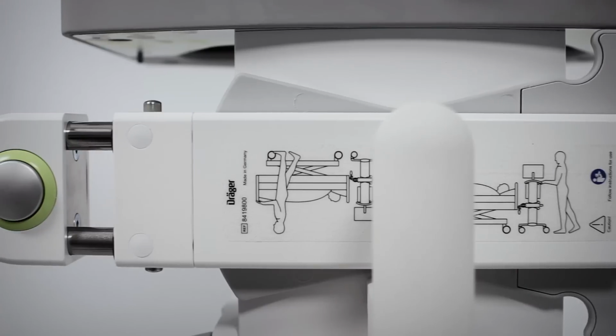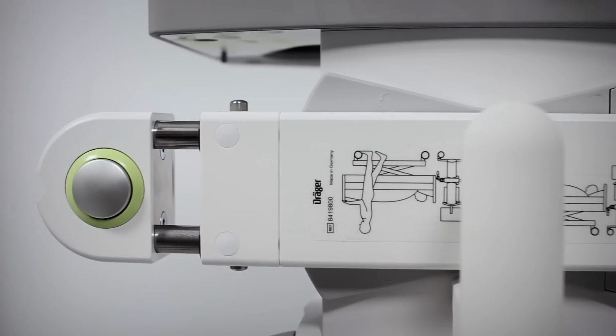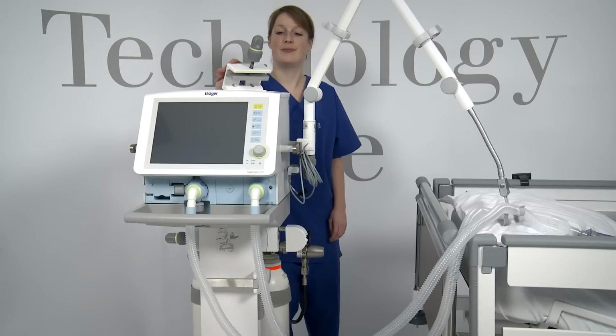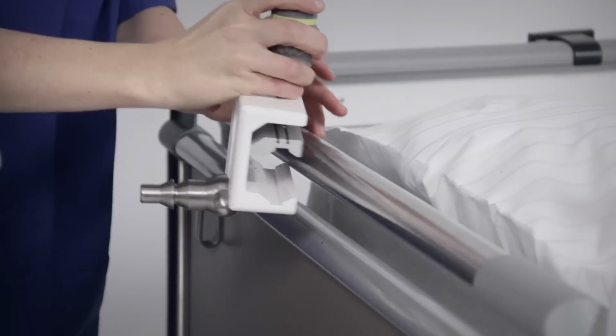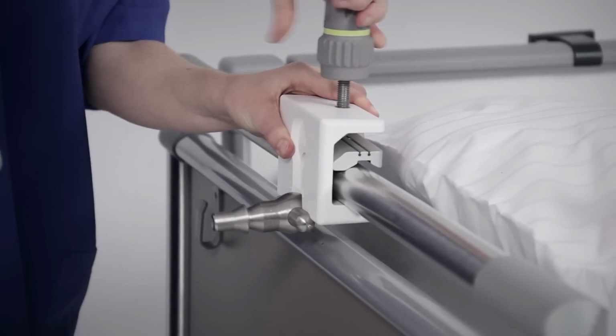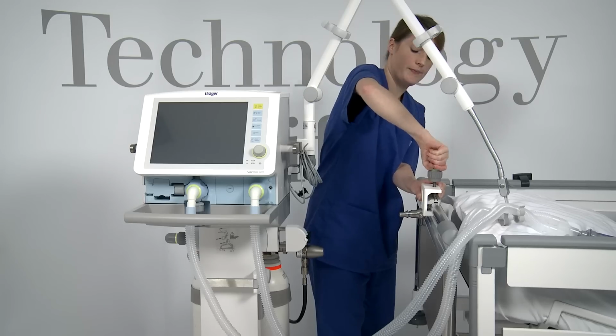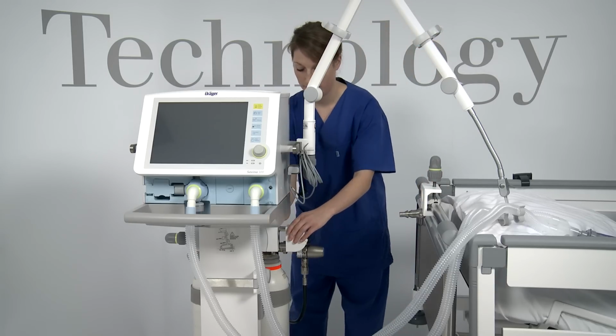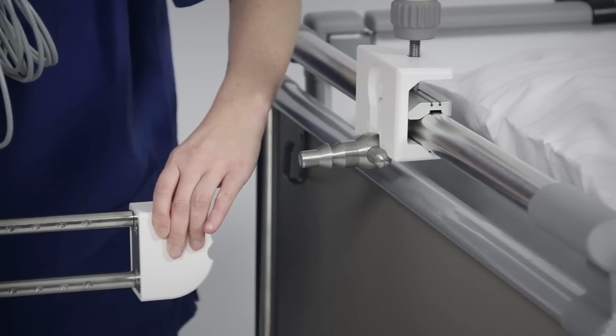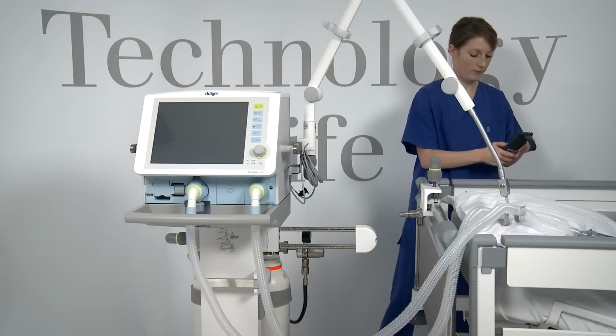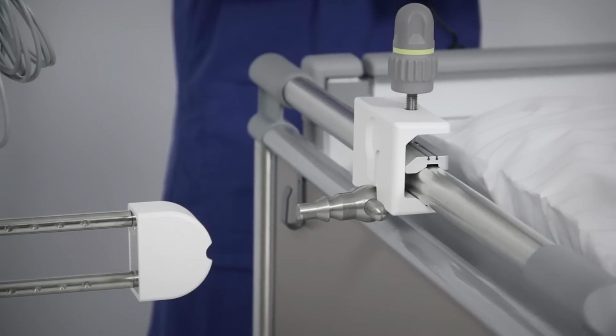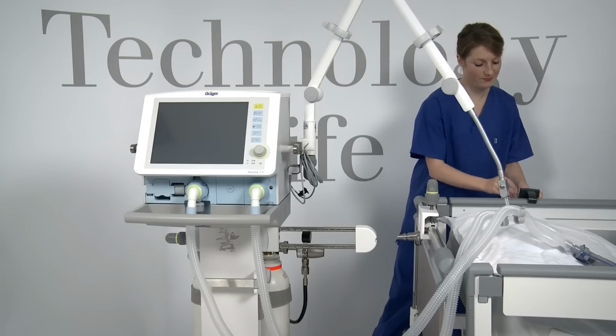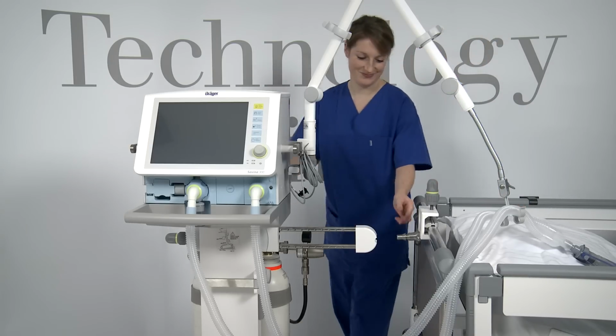It is a prerequisite that the device side coupling part is attached to the trolley. Attach the bedside coupling part to the rail or to the bar at the head end of the bed and align the coupling connector horizontally. Then couple the device to the bed. For that, lock the casters on the bed. Bring the device side coupling part and the bedside coupling part to the same height. Adjust the height of the bed or reposition the device side coupling part on the trolley column for this purpose.